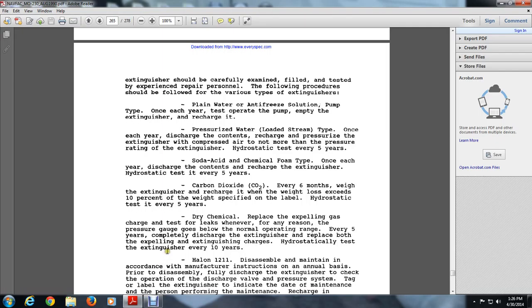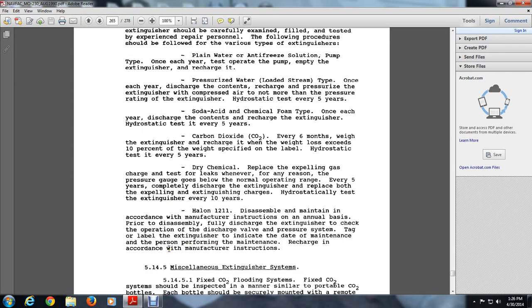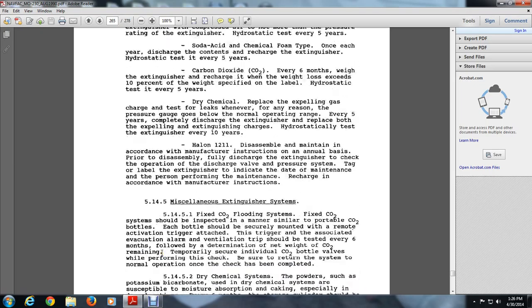Halon 1211: maintain in accordance with the manufacturer's instructions on an annual basis and prior to disassembly. Fully discharge the extinguisher, check the operational discharge pressure, and tag the label of the extinguisher to indicate the date of maintenance. Perform maintenance and recharge in accordance with the manufacturer's instructions.